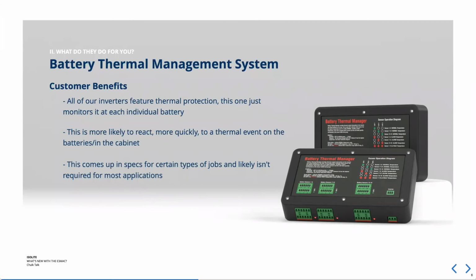I don't think this will be the standard offering or go on every job, but there are specs out there for certain jobs requiring positive confirmed thermal management of each individual battery. Previously we've had to take exception to that by saying our thermal management system is coupled to the enclosure, which acts as a surrogate for all the batteries. This allows us to directly meet it and say yes, we are coupled to every battery. We can meet that spec.